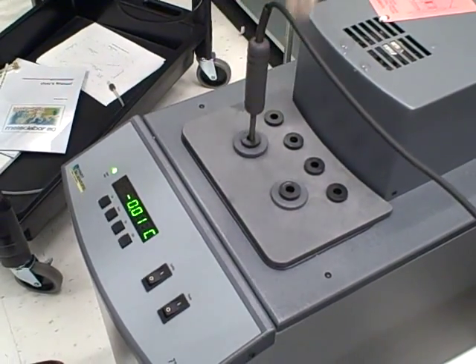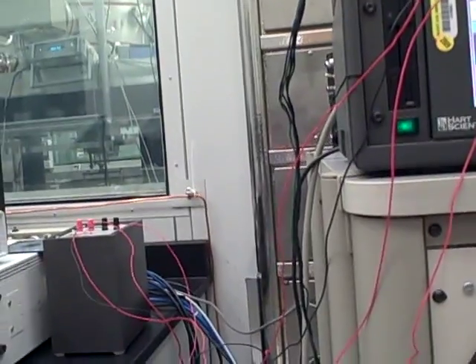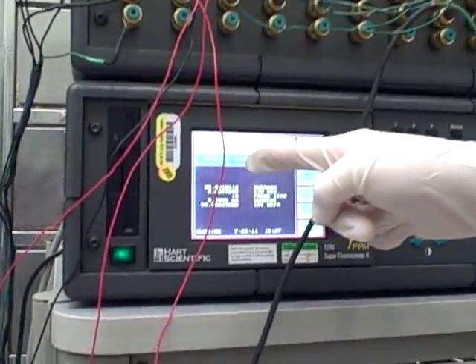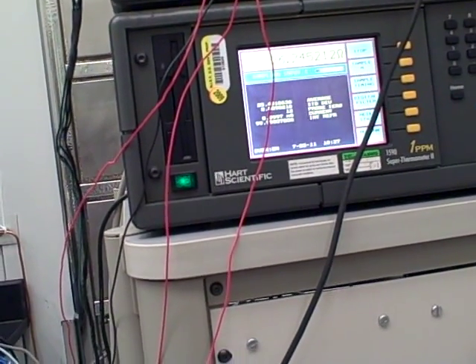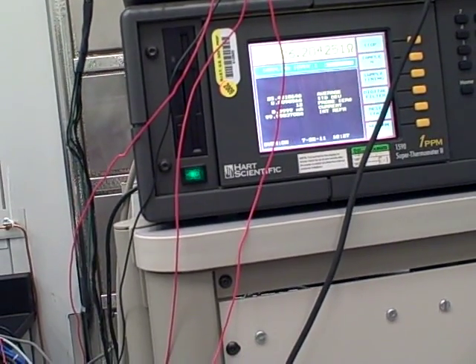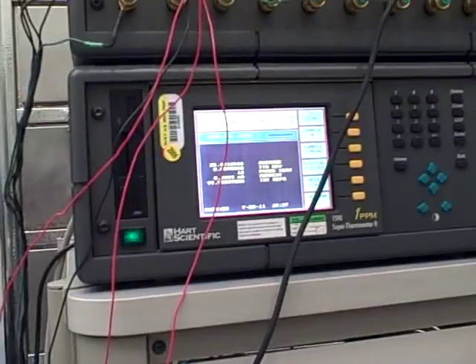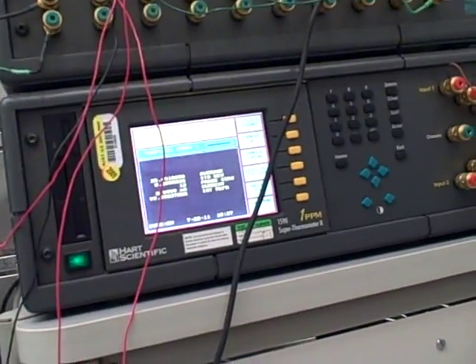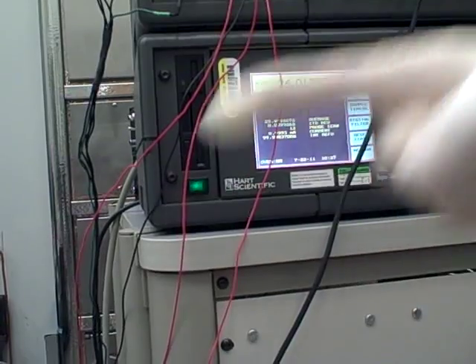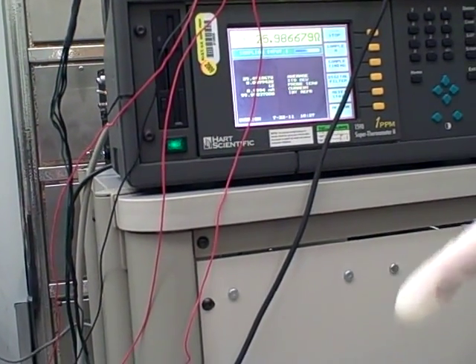And over here, this is the electrical resistance in ohms. So it's going to change here, and it will eventually settle down at something like 25.417. And when it stops changing, that's the resistance of this probe at the triple point of water. So when you measure a temperature, that's your calibration point.